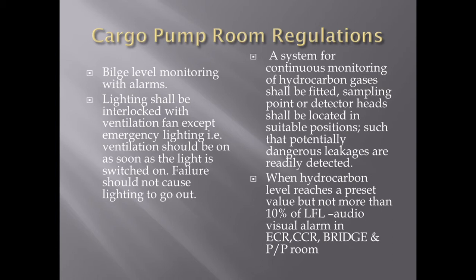First, bilge level monitoring with alarm. Wherever an alarm is involved, you need to know that the alarm will sound in the engine control room, the cargo control room, the bridge, as well as in the pump room itself. So we have a bilge level alarm monitoring system, and the audio and visual alarm will sound in all those places — ECR, CCR, navigational bridge, and pump room.